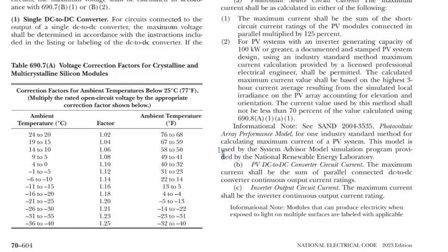All right, so if you're at the table, you'll notice that this table, and we will get to the other table, is about a voltage correction factor, right? Which is not something that you've looked at so far. But DC is affected by cold temperature, right? The old throw the battery in the freezer and you get more life out of the battery. That is not fake. That is real.